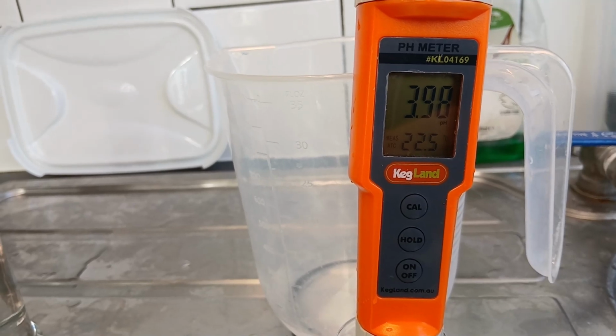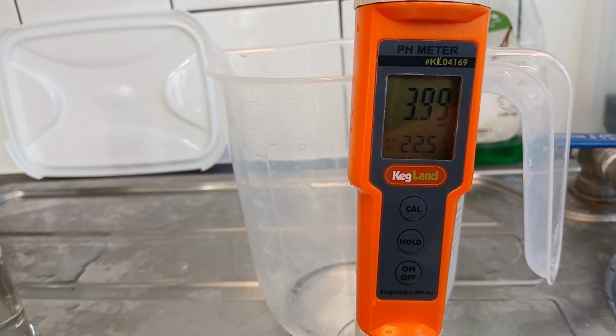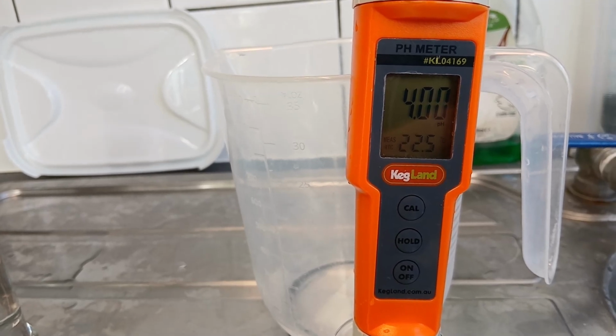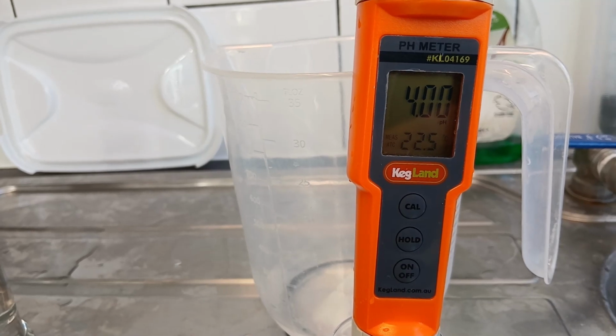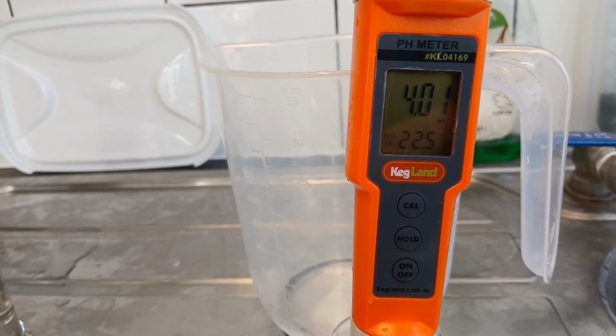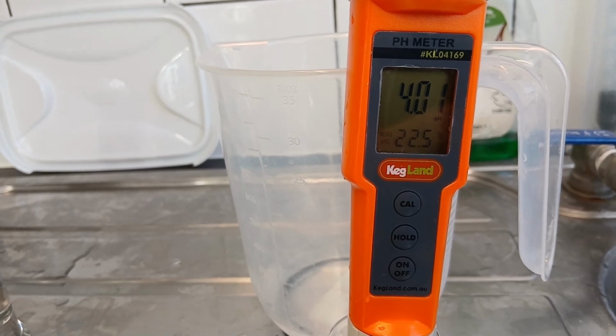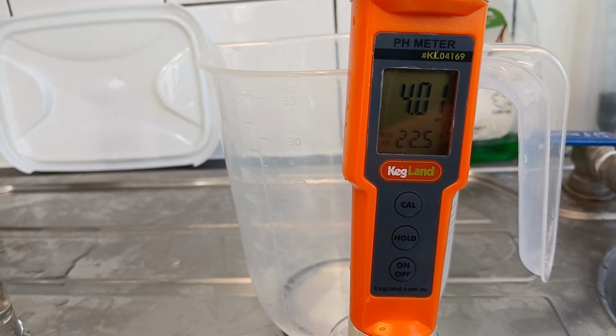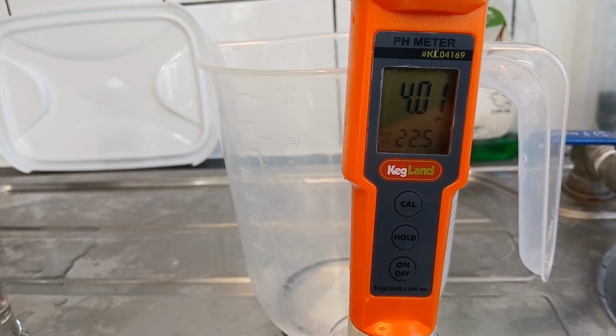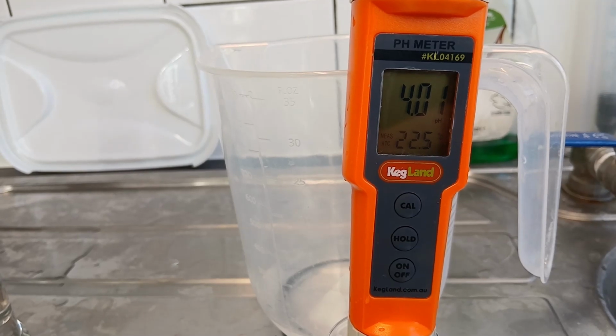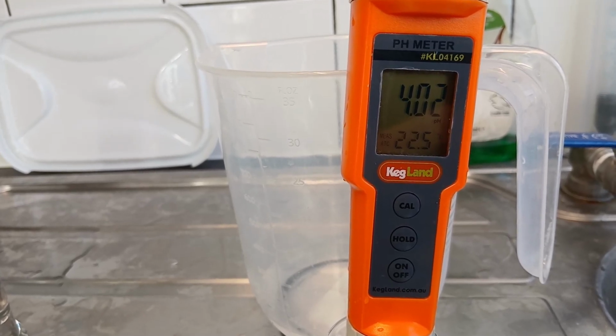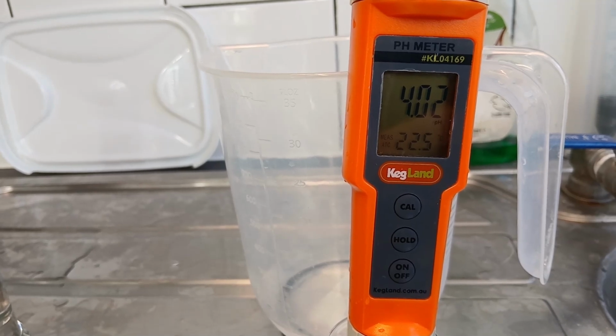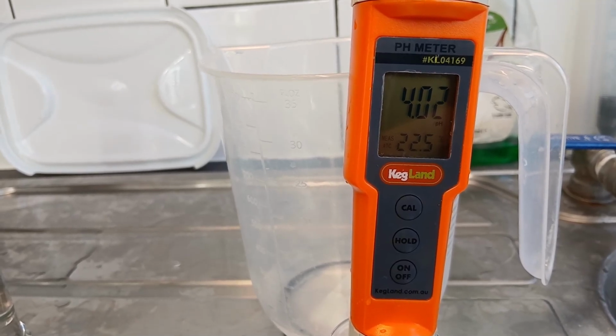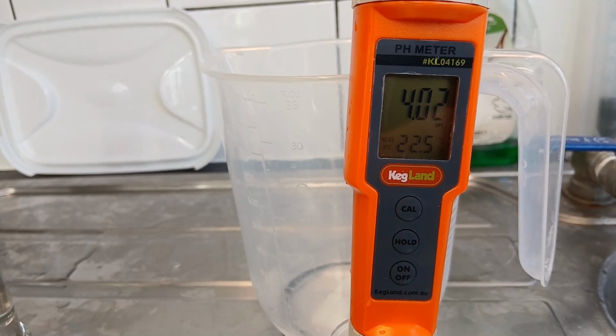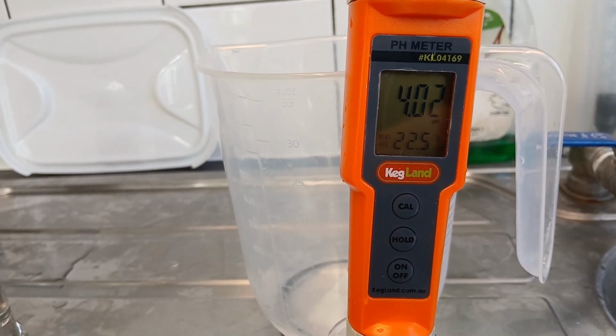Now with any instruments like this, it's not an exact science. You've got to remember it's never going to be 4.01 every time. It might be 4.03, 3.98, something like that. So after calibration at all points, we're coming back to a measurement of 4.01 with the 4.01 pH buffer solution. 4.02. It seems relatively stable. I'm happy with that. It's staying stable. I'm happy with that with a successful calibration.